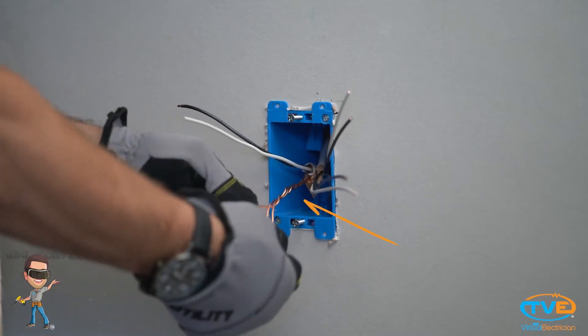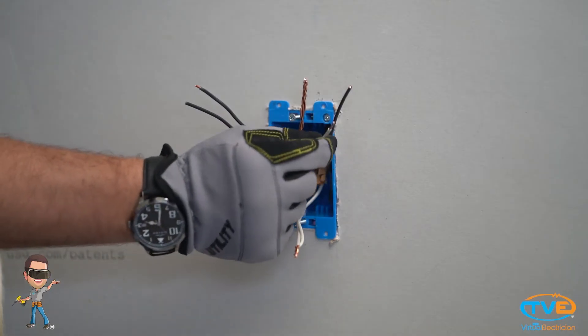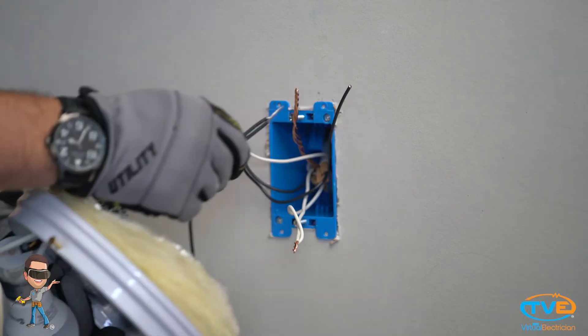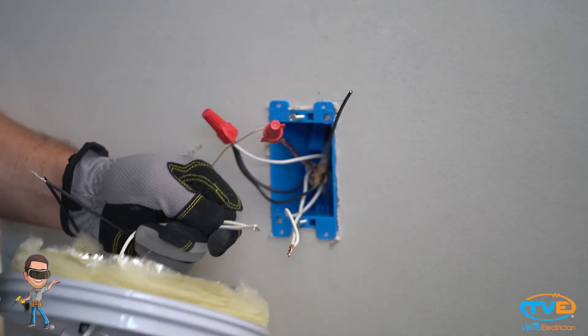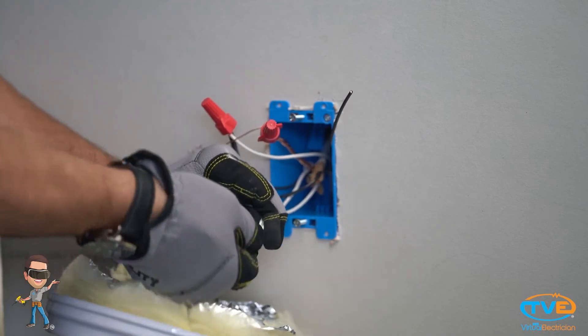Let's go back up to the fixture box. You will have all the grounds tied together the same way. You will still tie all your neutrals together, but you will have one wire that is white that will not be tied to the neutrals because it is not a neutral. The white wire going down to the switch box will be connected to the live wires, and the black wire that goes down to the switch box will be connected to the black wire of the fixture. Bare to bare, the white fixture wire goes to the neutrals because we still need a return back to the panel. And that is how you install a fixture on a switch loop.